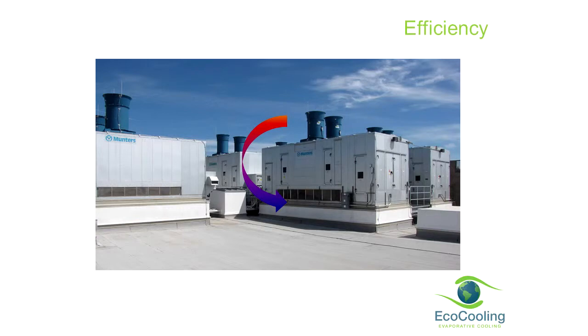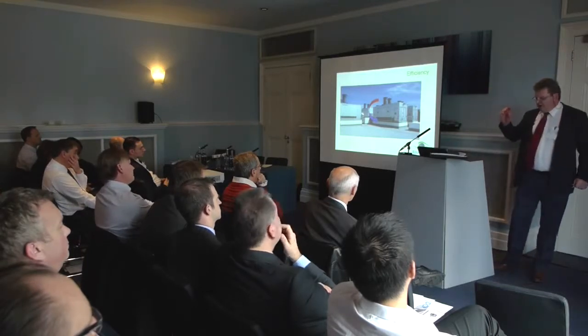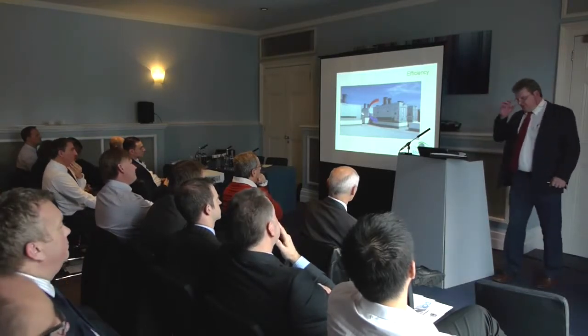A perennial problem, and I happen to put, this is a big indirect cooler, but it applies to everything. One major problem in cooling design, particularly in big data centres, is that I'm making all these assumptions based on fresh air temperatures. Whether you're putting chiller plants in, DX with condensers, or direct or indirect, if you've got any level of density of your plant equipment outside, preventing that recirculation of air is paramount to exploiting the maximum amount of free cooling.